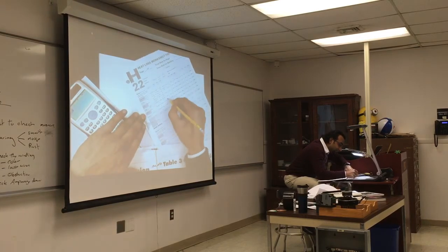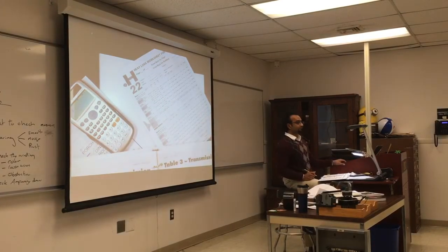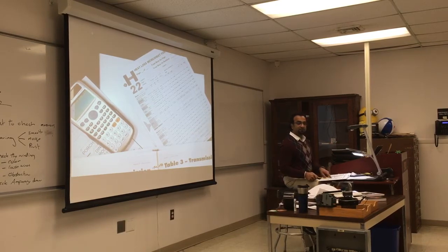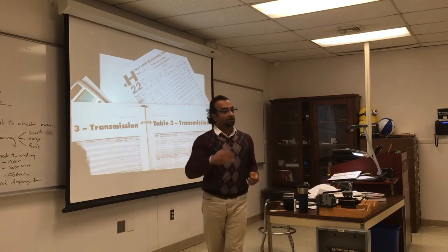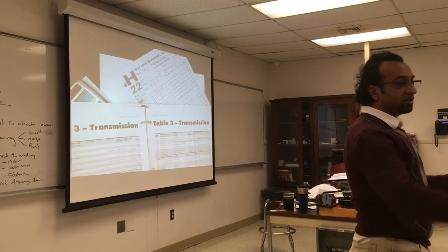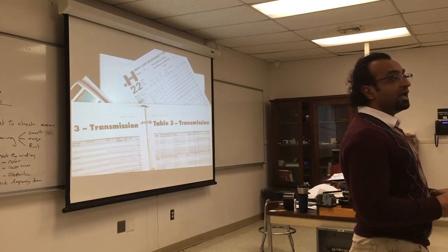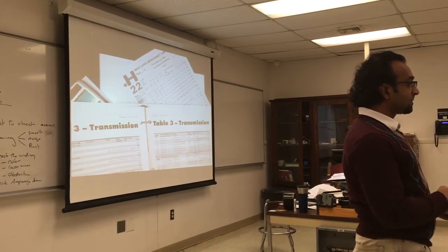What is DTD? It's going to be the same, it's not going to change at all. 75, 75. We don't have slab. So we're assuming that's just one story and it's not insulated above it? If it's a one story and the top is not heated, you're going to lose heat from that. So it's like a ranch. If the second floor is heated, you do not have heat loss from the ceiling.